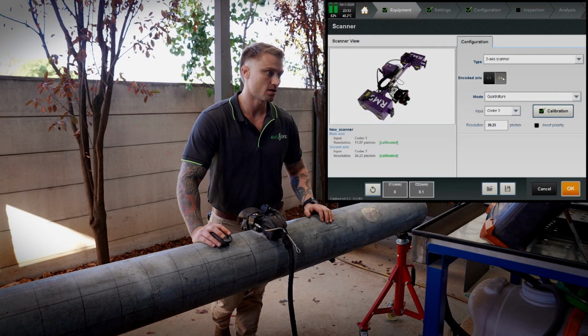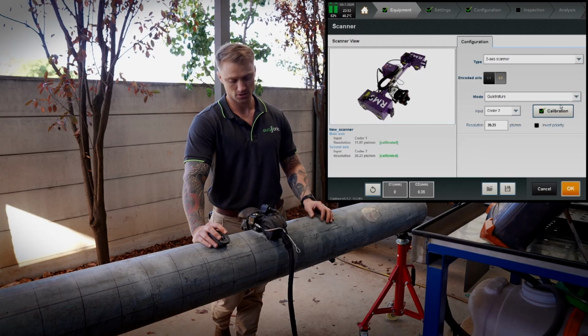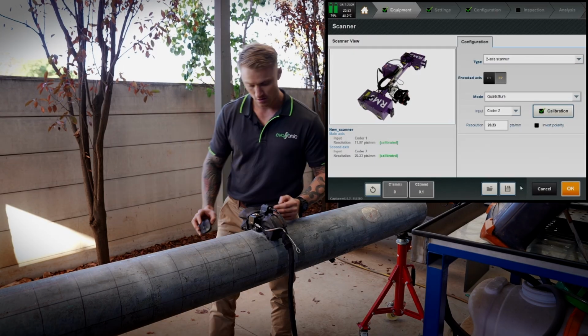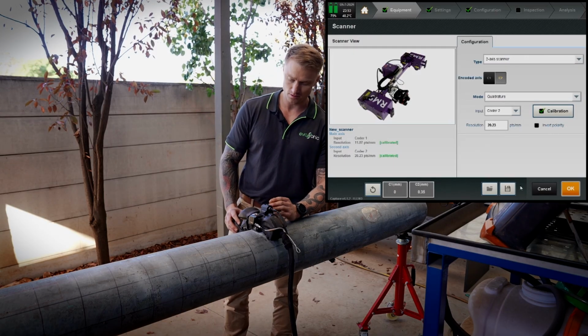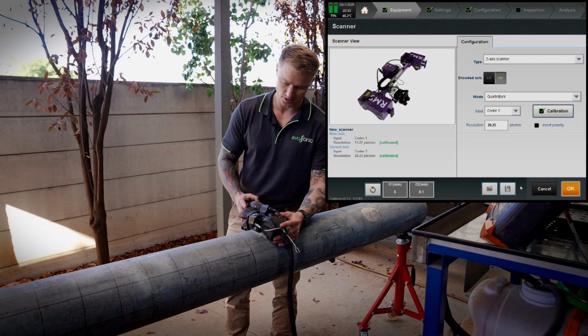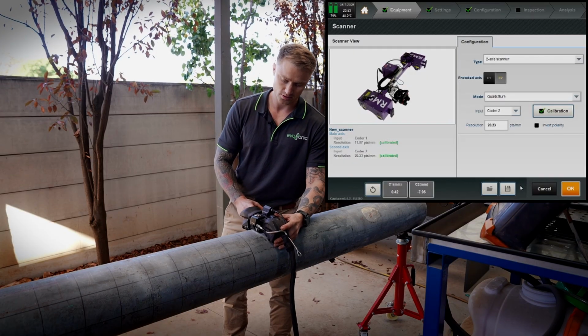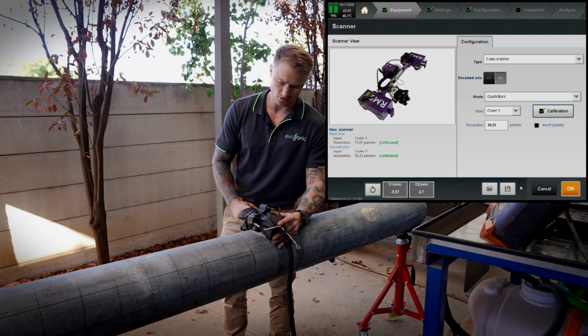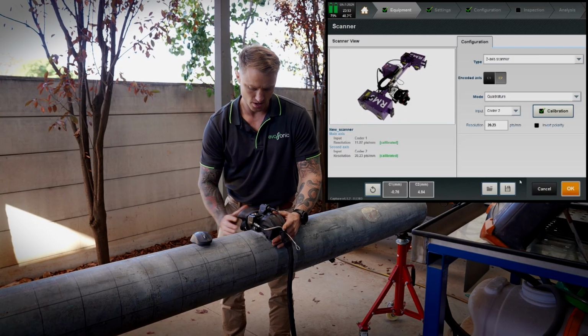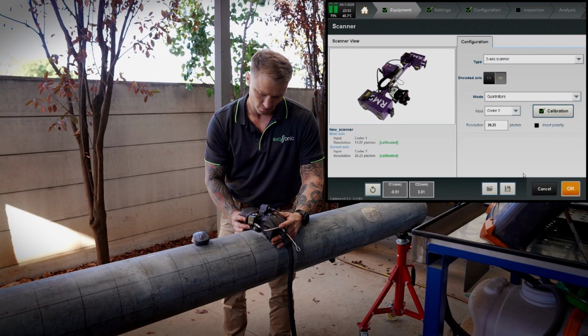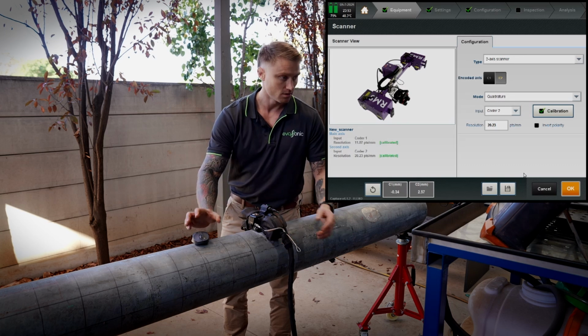From that, I'm going to calibrate and start the calibration process. What I like to do is get my ARC at top dead center with my lights. You'll see the lights walk in, and once I only see that center light, I know the ARC is sitting at 12 o'clock, or TDC.